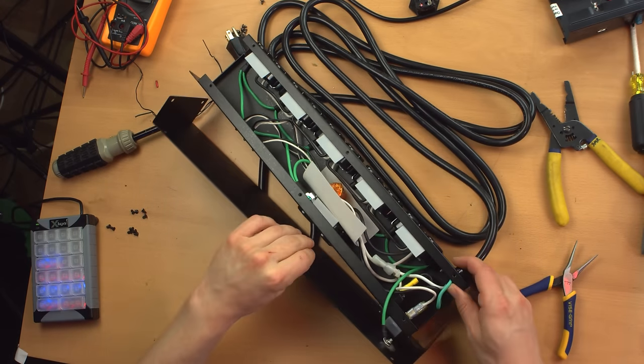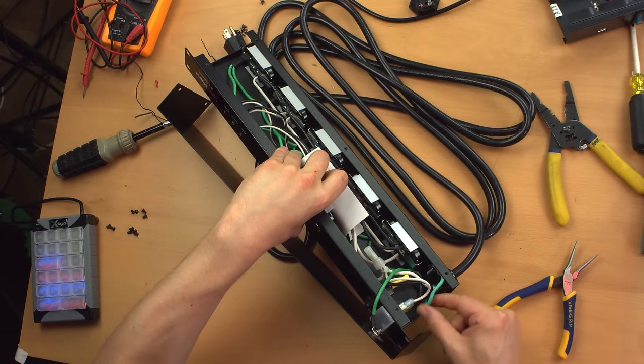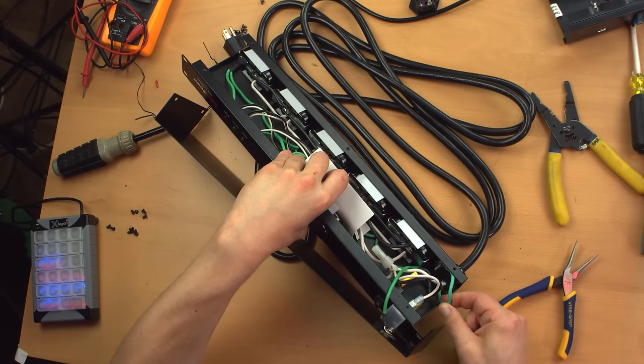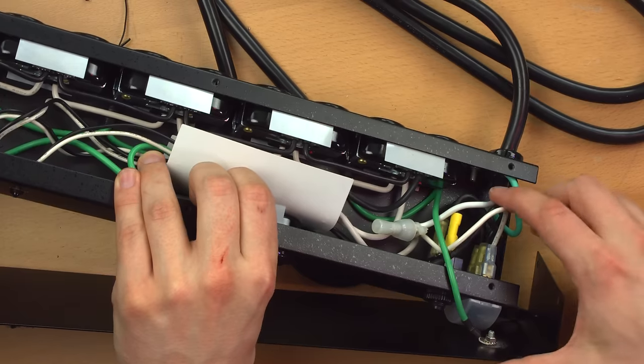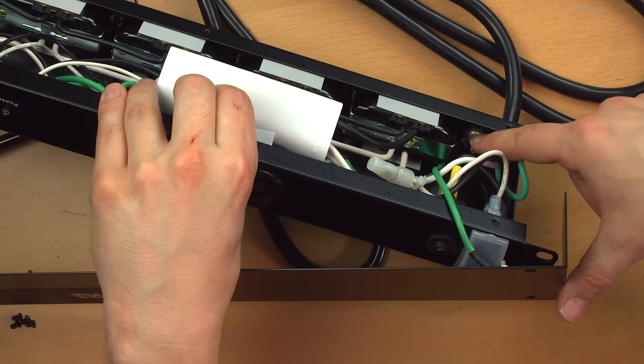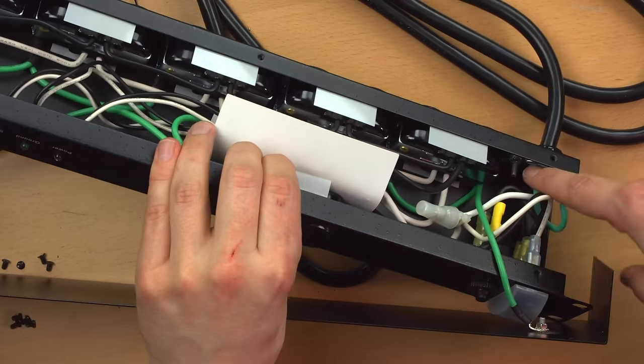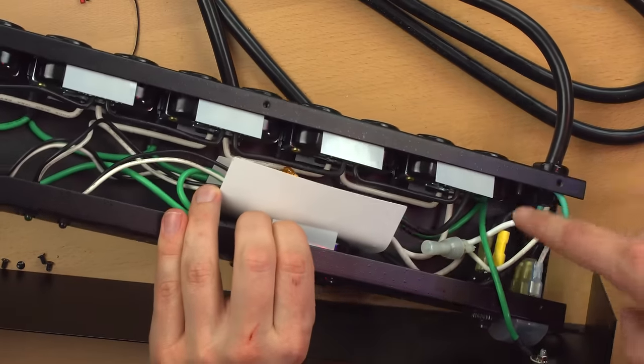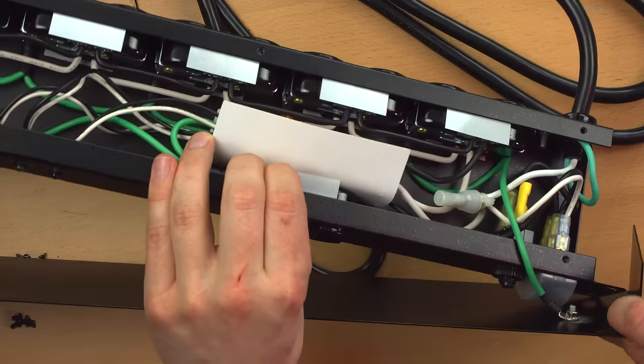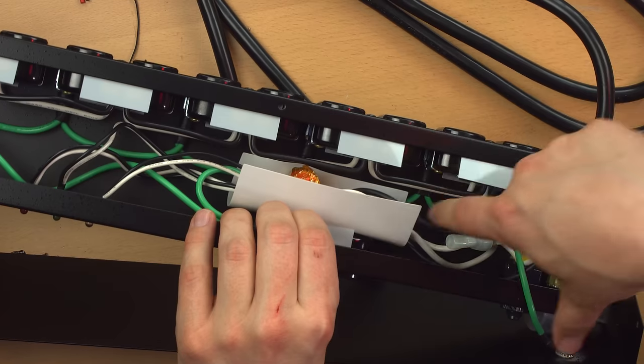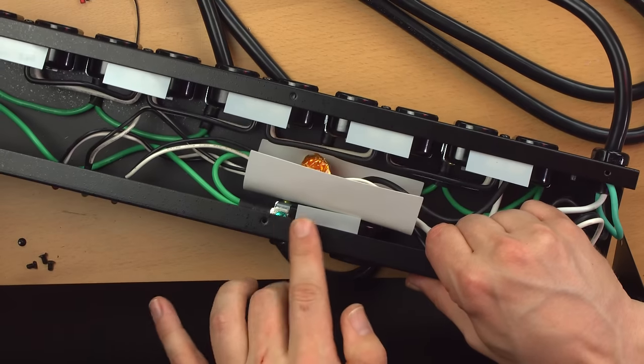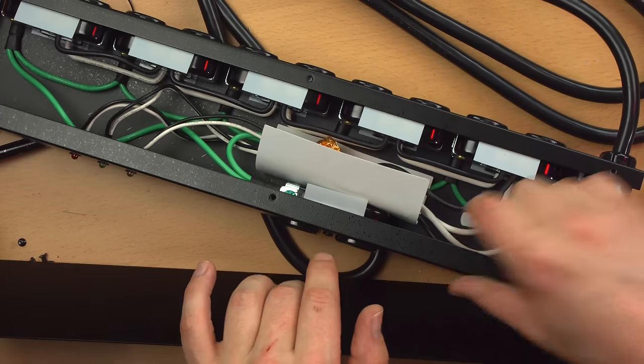And just incidentally, the grounding wire comes in from the cord set, and it looks like that's a full 12 gauge. It hits a lug going right through the back of the unit. And then from that lug, it comes around and forks off, one to the top of the unit, and then it jumps from receptacle unit to receptacle unit, and like I said, back around the front to this receptacle unit.